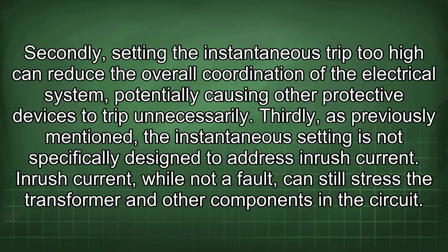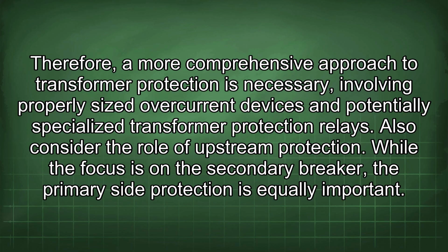Thirdly, as previously mentioned, the instantaneous setting is not specifically designed to address inrush current. Inrush current, while not a fault, can still stress the transformer and other components in the circuit. Therefore, a more comprehensive approach to transformer protection is necessary, involving properly sized overcurrent devices and potentially specialized transformer protection relays.